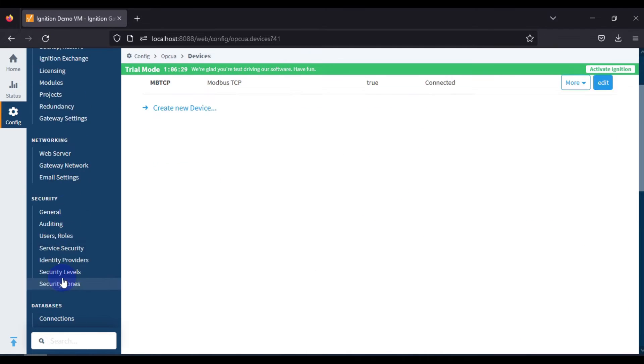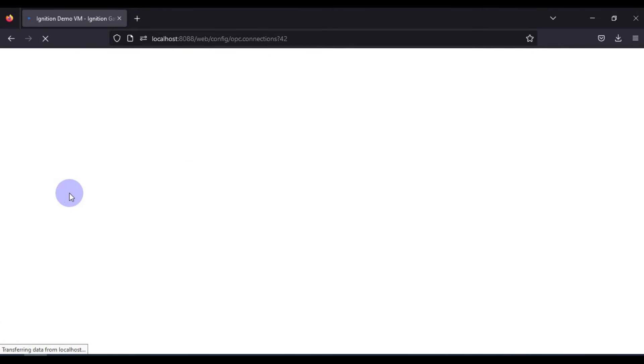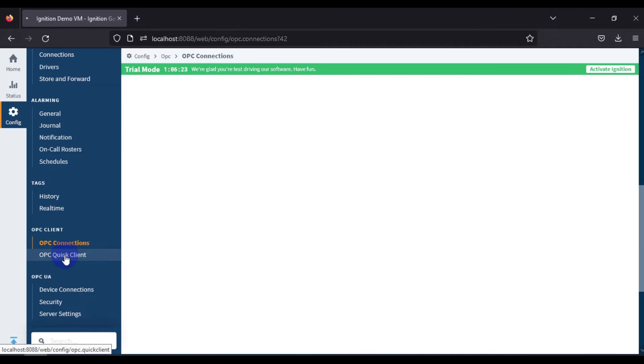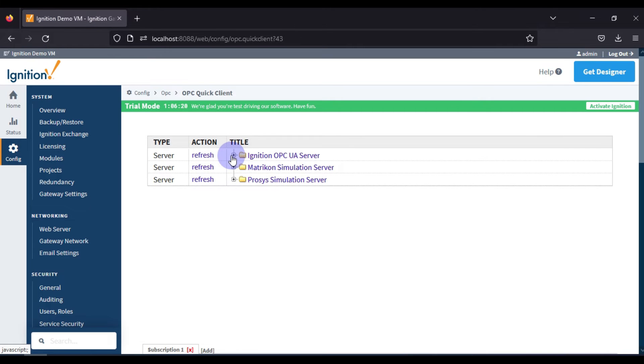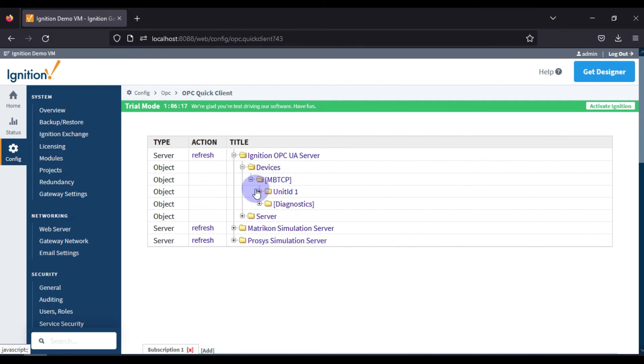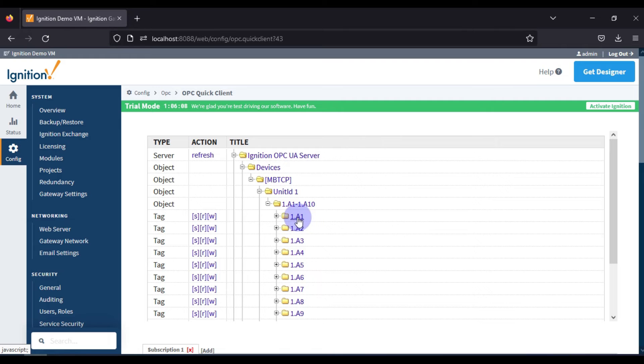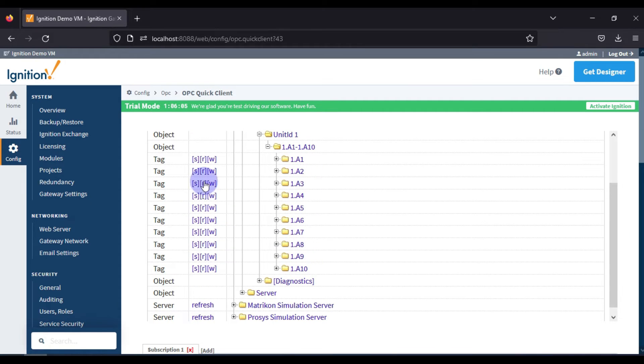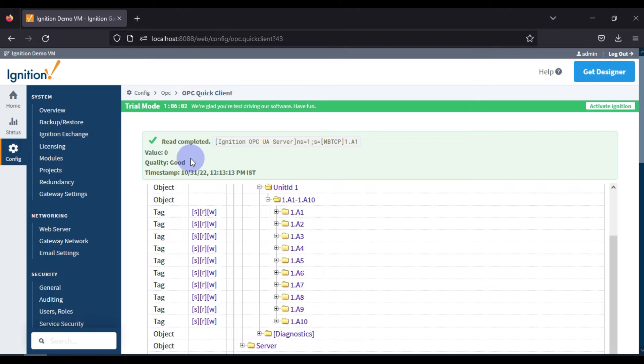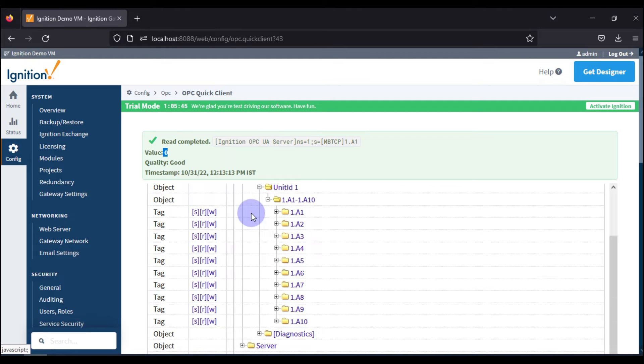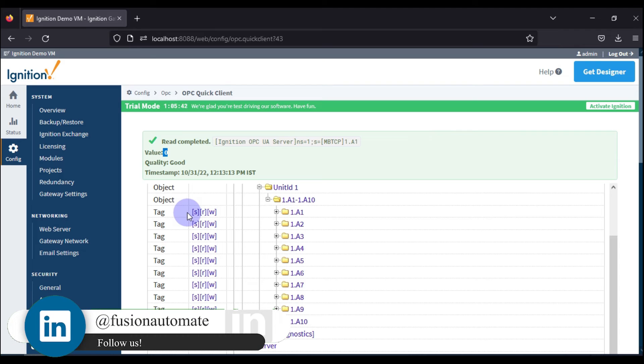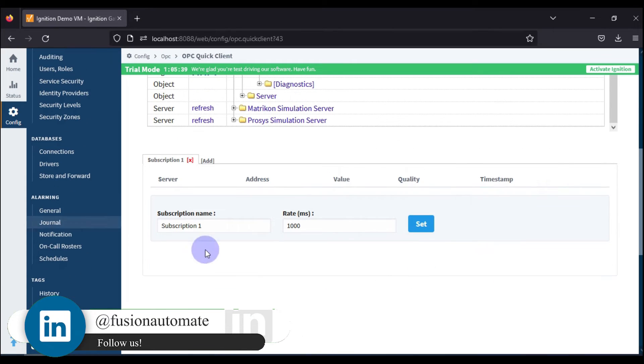It shows disconnected momentarily and then connected again. Now we go back to OPC Quick Client, then Ignition OPC UA Server > Devices > Modbus TCP. You can see our device with Unit ID 1. Expanding it shows tags A1 through A10. If you press the R button you can see the value 0. R stands for Read, W stands for Write, and S stands for Subscribe.